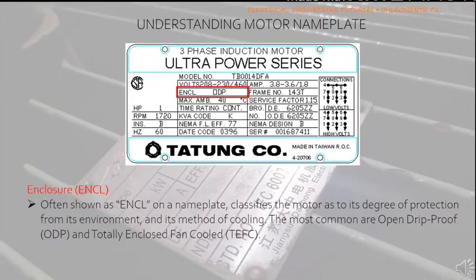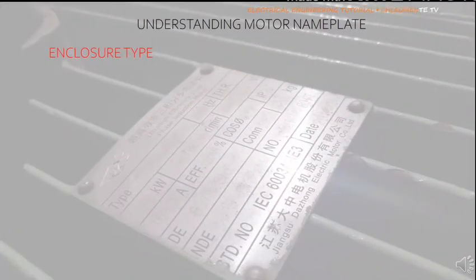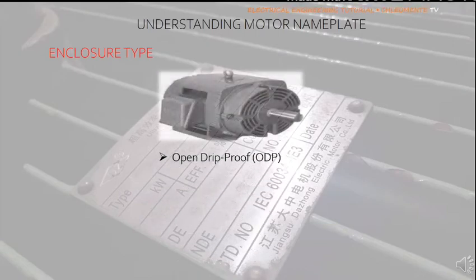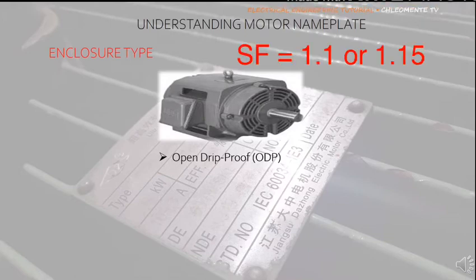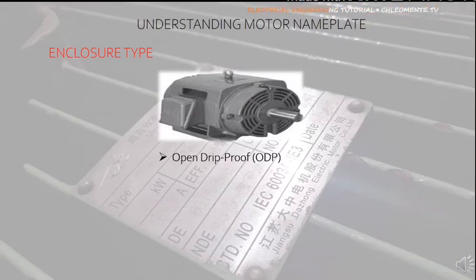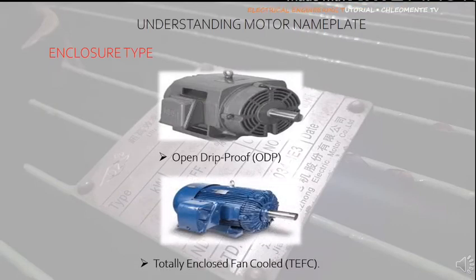Enclosure, denoted by ENCL, classifies the motor by its degree of protection and method of cooling. The most common in industry are ODP (open drip proof) and TEFC (totally enclosed fan cooled). ODP motors typically do not overheat due to openings in the casing through which air flows directly over the winding, making them more efficient with a service factor of 1.1 or 1.15, but they are not recommended for outdoor installation or dusty environments. TEFC motors have totally enclosed chambers cooled by an external fan on the non-drive end, and are highly recommended for outdoor installation.